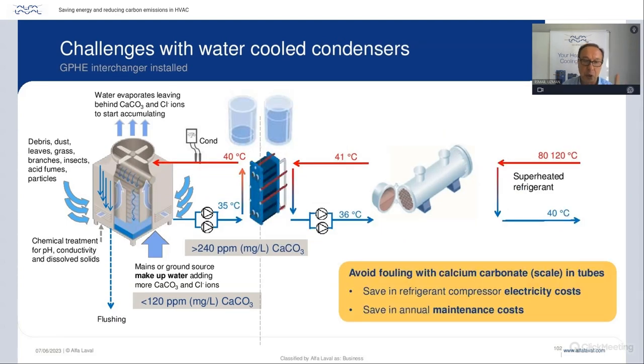Now, what we're proposing, as I showed you before, is to break the circuit with a heat exchanger. The calcium carbonate here stays in solution because the wall temperatures are under 40. And where the condenser is, between the heat exchanger, we do need a set of additional pumps, yes, but this is lifelong clean. The condenser, the chiller efficiency does not drop because of calcium carbonate. And even if it's 120 degrees superheated refrigerant gas, there is no calcium here. So this is a great way to save in electricity costs and also save in maintenance costs. But electricity is by far the biggest saving here.